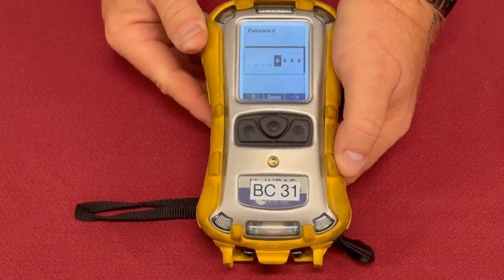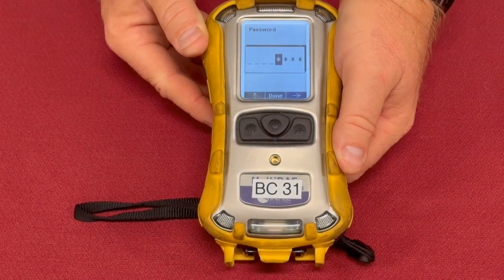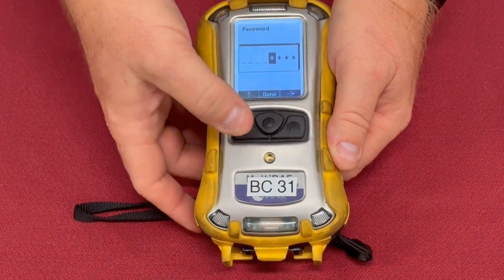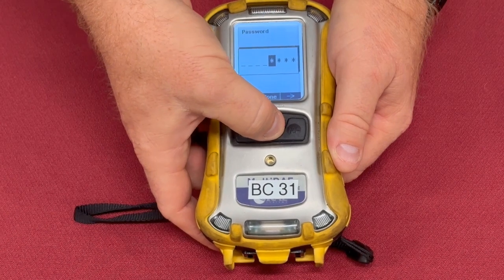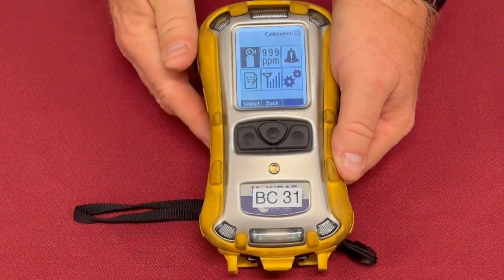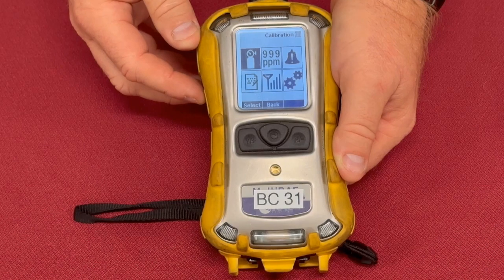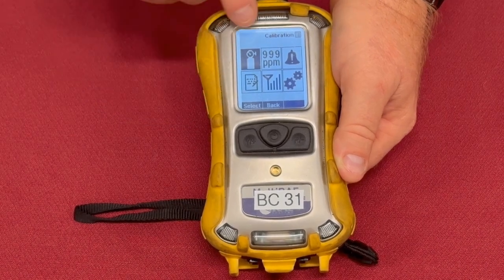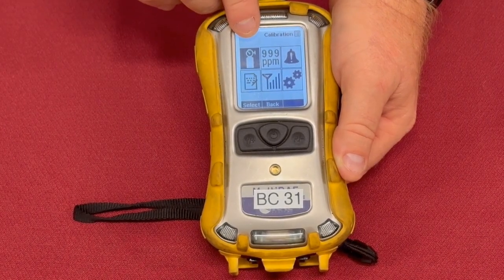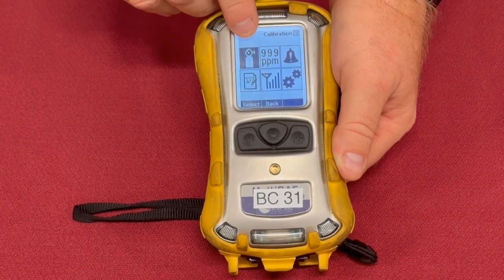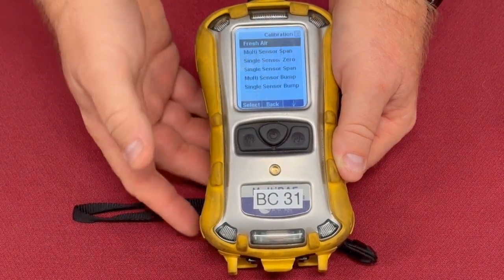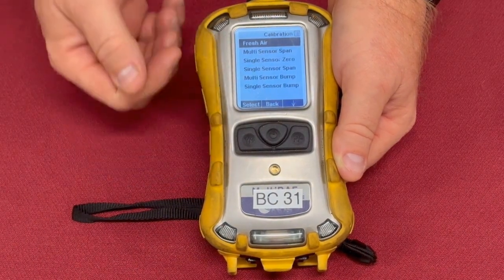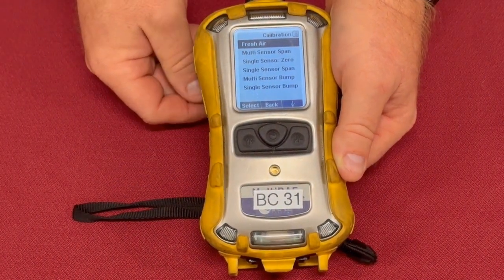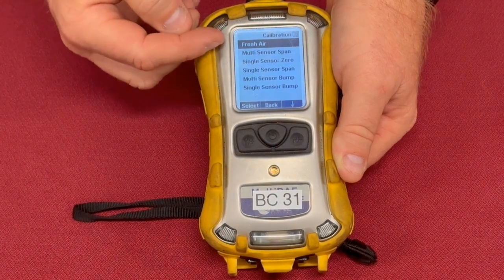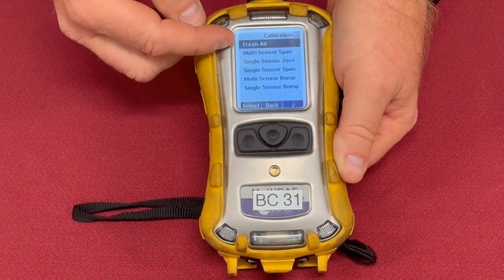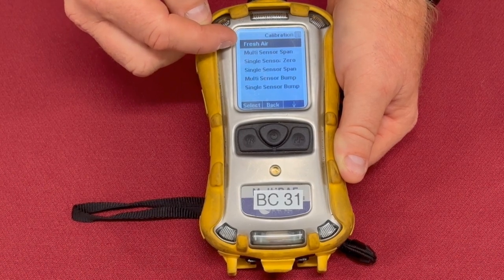Now we have the meters locked out, so you can't go back and mess with any of the programming. However, all you need to do at this point is just hit done, and it will go on through and let you do the things that you're allowed to do, one of those being calibration and bump testing. The little cylinder here is the calibration and bump screen. It's already highlighted. Just hit select, and then a menu comes up. Now, you notice I've talked about calibration and bump testing, and as we come down the menu, you could redo a fresh air setup, so that allows you to redo it if you started it in a dirty environment.